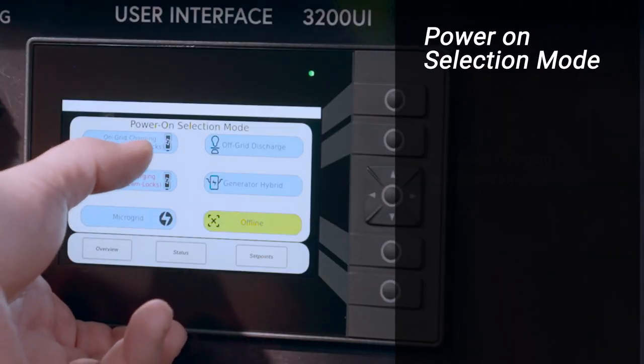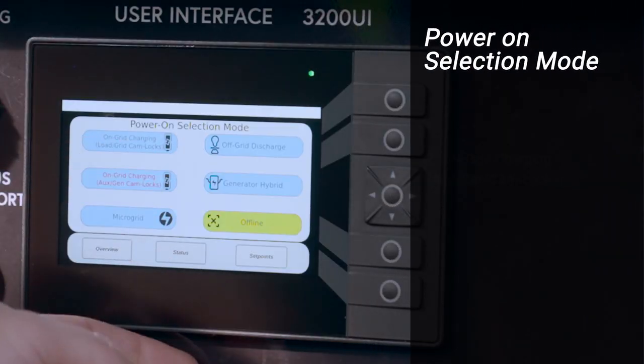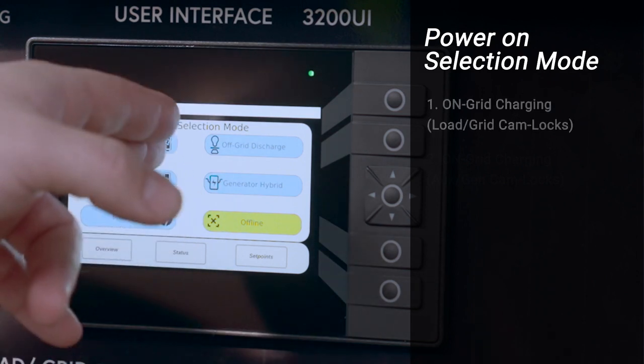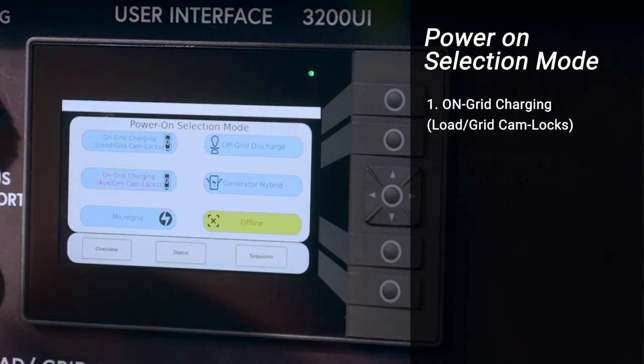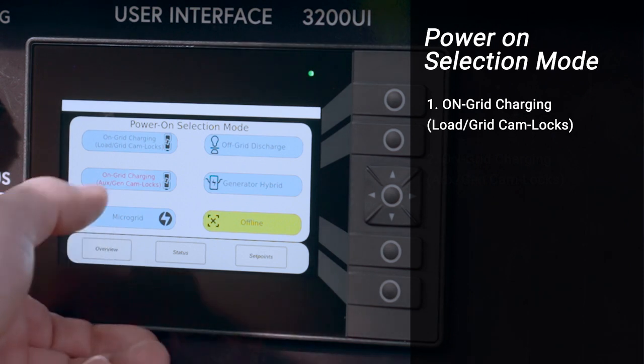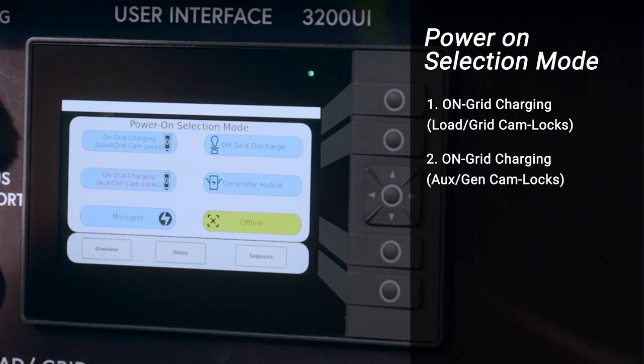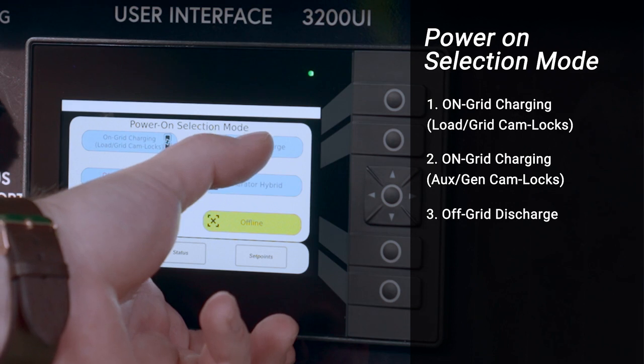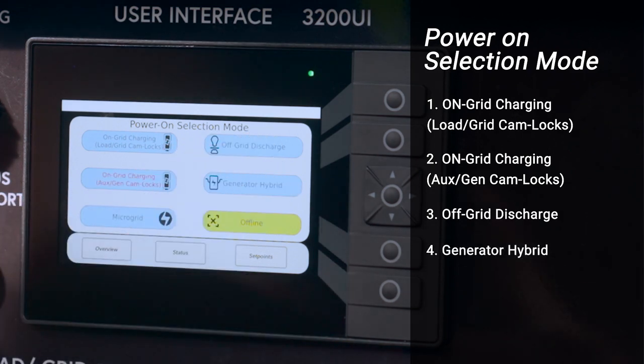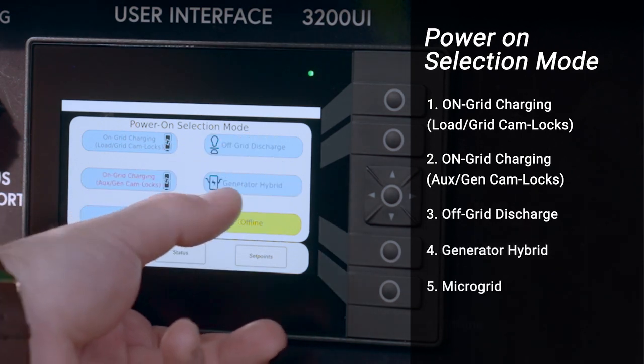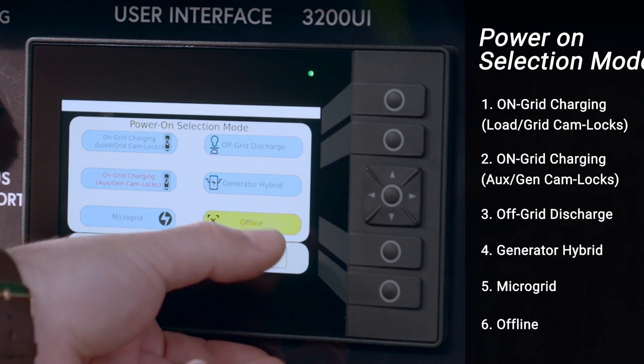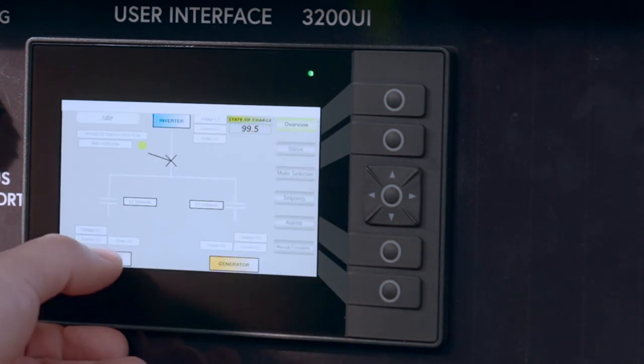Next, I want to go through the user interface navigation and some of the screens that are currently programmed on the SBR30-150. On power up, the first screen you will see is your mode selection. Right now we have 6 modes programmed. You have your on-grid charging for your load cam, which is also an on-grid discharge. You have your on-grid charging for your auxiliary cam. You have your off-grid discharge, your generator hybrid mode, your microgrid mode, and then your offline mode, which will be turning the machine off.